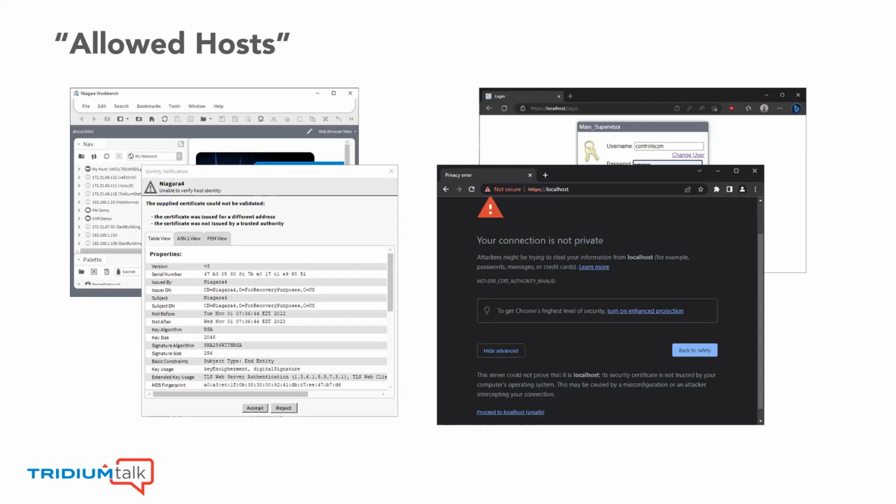There's now that default certificate, and you cannot remove it. When you hit reset, it will exist. That is so that there's always some certificate, and that'll keep people from accidentally locking themselves out. To date, you have that certificate. I believe its alias is Tridium, not default, and that will still remain when you upgrade.